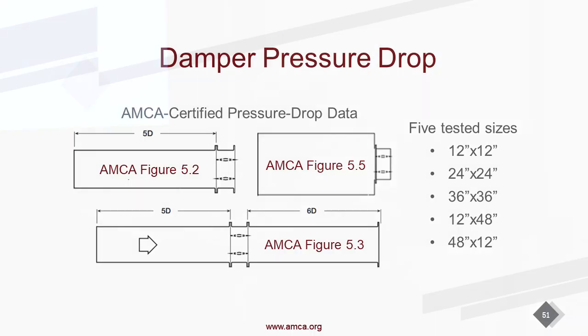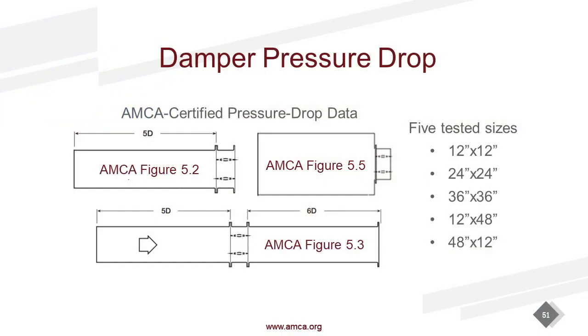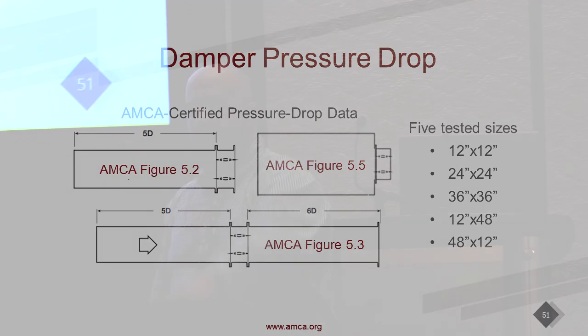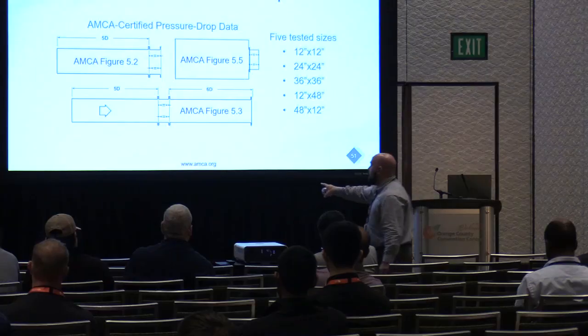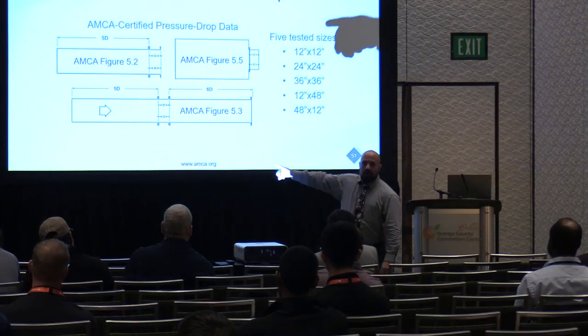I can take all my damper manufacturers and put them side by side. We test the same 5 sizes for all manufacturers, and you're required to pick a test figure and publish at least one of them. You can optionally publish 2, you can optionally publish 3. There's no limit. This is the most common one on the bottom. That's 5.3. It's a fully ducted inlet and a fully ducted outlet, straight duct run. For my designers, how many times do you actually put that on your drawings? But when you're estimating the pressure loss of your damper, this is the number you're using, right?